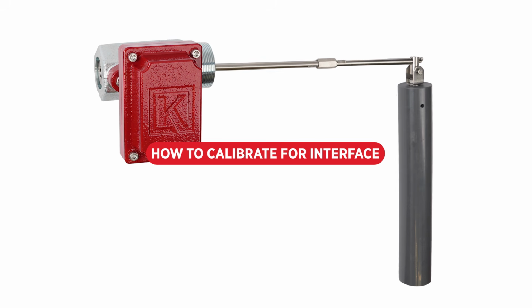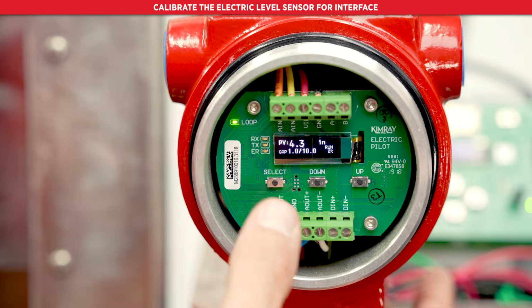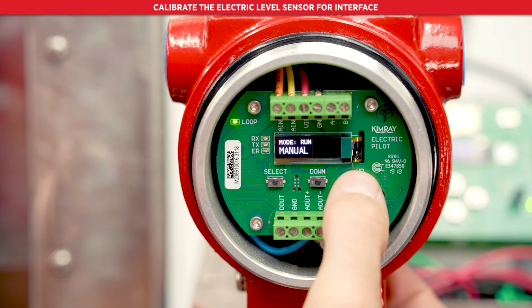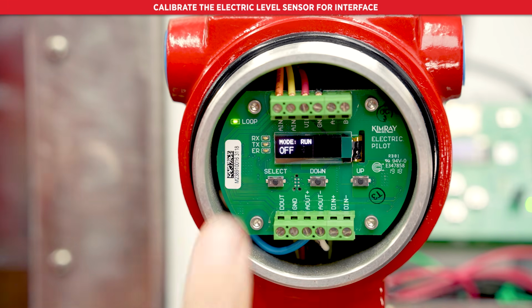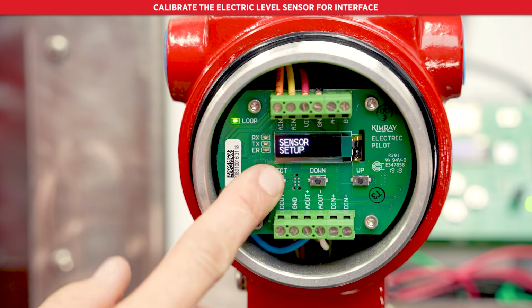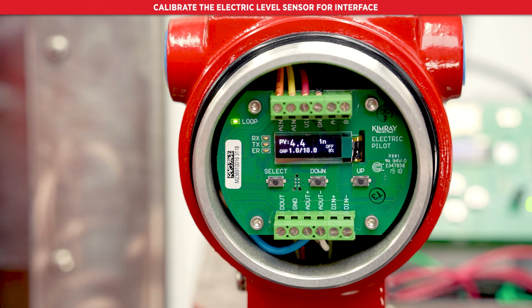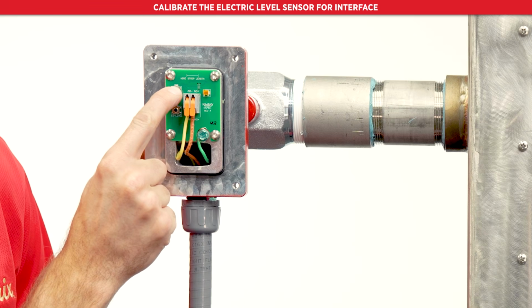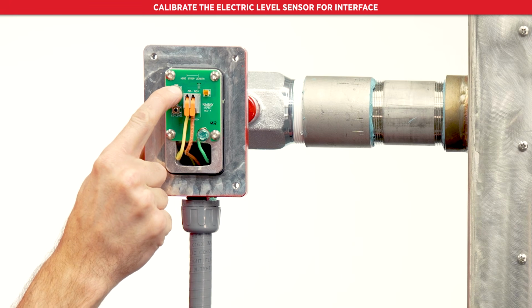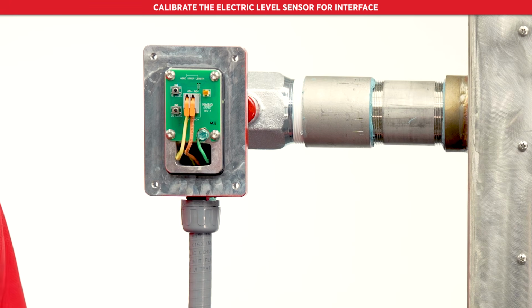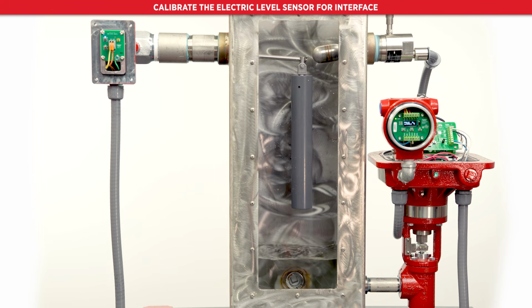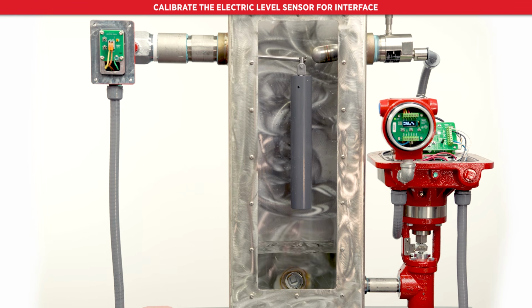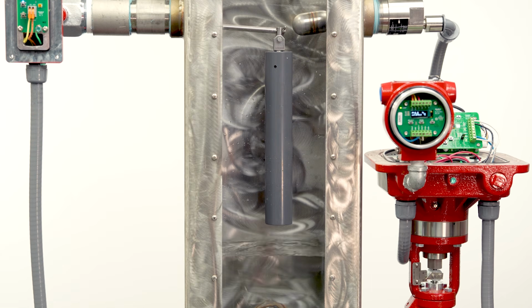If you're setting up for interface control, you will now need to calibrate the electric level sensor for interface. First, turn the pilot back to off mode. To quickly get back to the home screen, hold select for 3 seconds. Hold down the high level button on the sensor for 5 seconds. Once the LED begins to flash, release the button. While the light is on, increase the liquid level in your vessel until you can confirm that it is above the displacer.